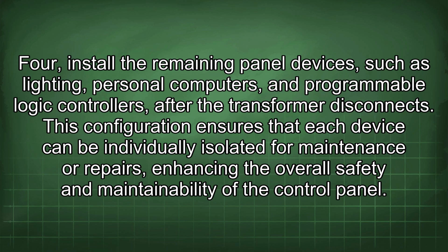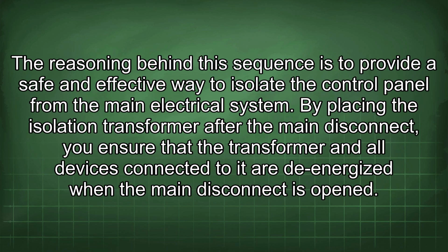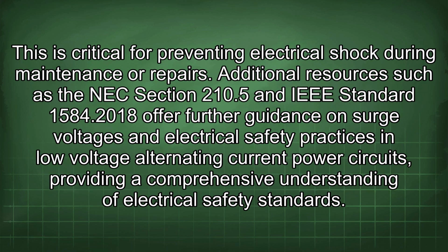The reasoning behind this sequence is to provide a safe and effective way to isolate the control panel from the main electrical system. By placing the isolation transformer after the main disconnect, you ensure that the transformer and all devices connected to it are de-energized when the main disconnect is open. This is critical for preventing electrical shock during maintenance or repairs.